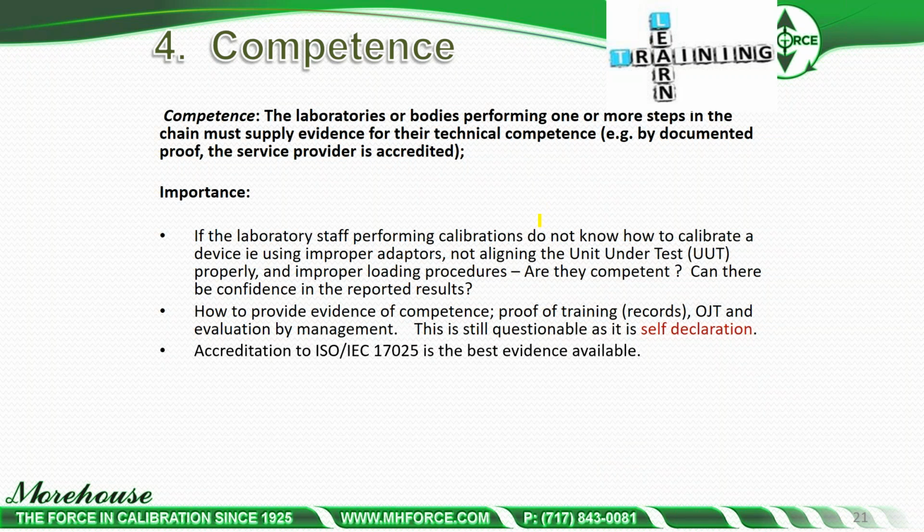Can there be confidence in the results? How to provide evidence of competence? You can do this by proof of training records, on-the-job training, evaluation by management. The problem with that is it's still questionable. It's self-declaration. ISO 17025 accreditation is probably the best evidence. It's not the only evidence for competency, because the auditors do not check for everything.